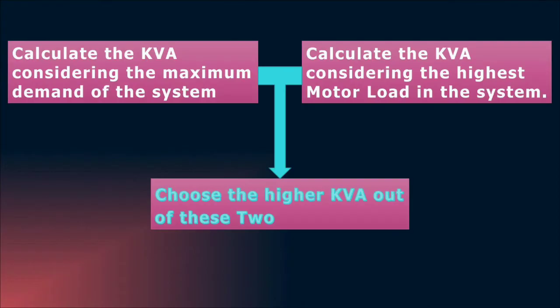And now we are going to see the methods of selection of rating for a transformer. The required kVA value of the transformer is chosen as the higher value of kVA arrived from two different methods. Now we can see the two different methods. In method 1, the transformer kVA is calculated by considering the maximum demand of the system. In method 2, the kVA rating is calculated by considering the kVA required during the starting of the highest rated motor in the electrical system plus the kVA required for the balanced electrical loads.